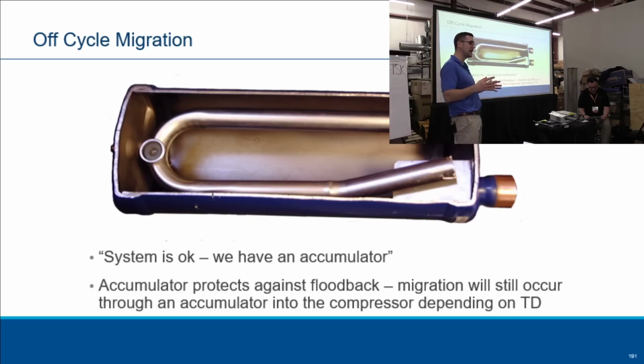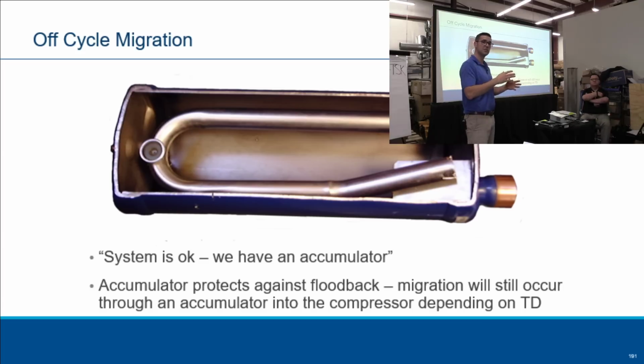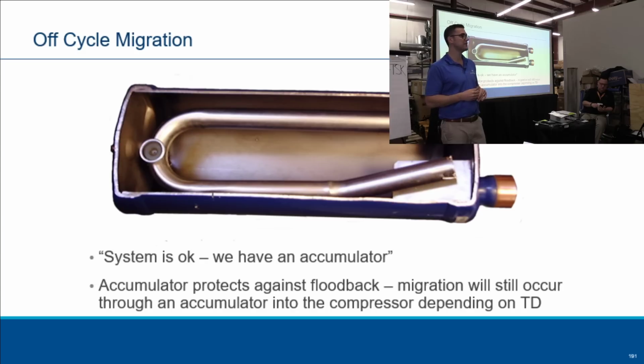I did it all. Thought I did it all right. I leave the site, I check all my superheats through all loads. So when you're doing a system, you want to make sure your superheat, your discharge temperature, through defrost, through everything. You make sure through all the loads. Three months later, I get a call from my boss. You've got to go back to this Rexall. I go up onto the roof, and I've got another failed compressor. I'm like, what is going on here? So I call up another journeyman, and he's like, is there an accumulator on there? I'm like, yeah, there's an accumulator. What kind of failure was it? Oh, it was a really bad burnout. He's like, your accumulator. What do you think happened?